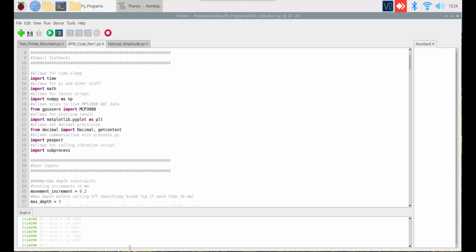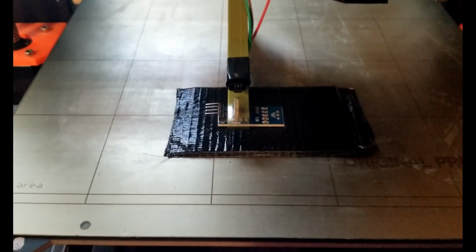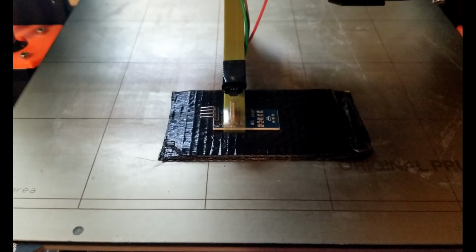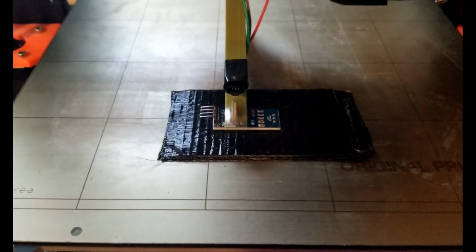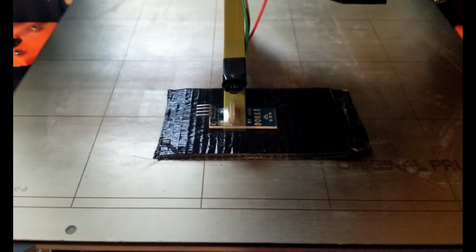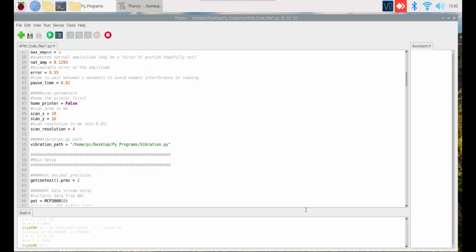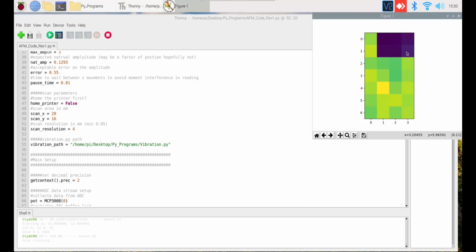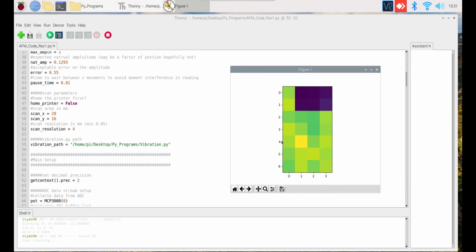So you'll see the tip starts to oscillate, and then after a couple seconds the head will start to creep across the surface, taking a measurement at each point determined by the resolution. Because a high-resolution scan takes quite some time, on the order of an hour, I decided to lower the resolution for this example. So what you're seeing here at the end is just at the very top right corner.